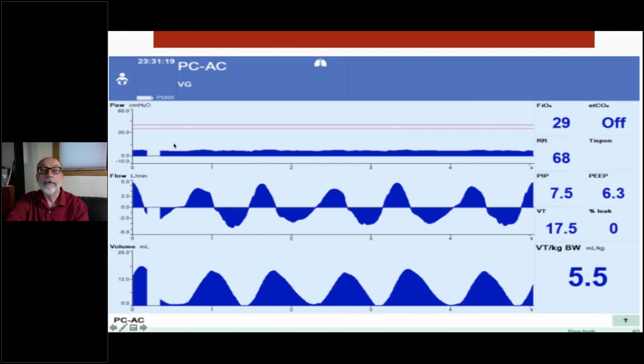This baby is not receiving any significant pressure from the ventilator, but yet is generating a big tidal volume, right? And what this scenario shows us is the ventilator is doing exactly what it's programmed to do. When the baby generates tidal volume that's more than the set value, the pressure comes down, down, down until the ventilator is generating virtually no pressure. If the baby is tachypneic and retracting, the baby needs a bigger tidal volume. If the baby is comfortable, then we should probably extubate.